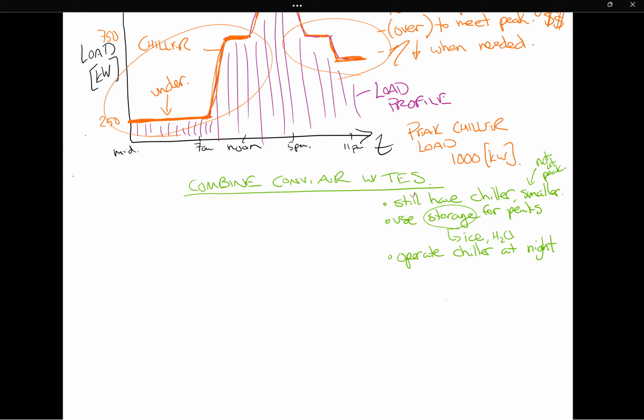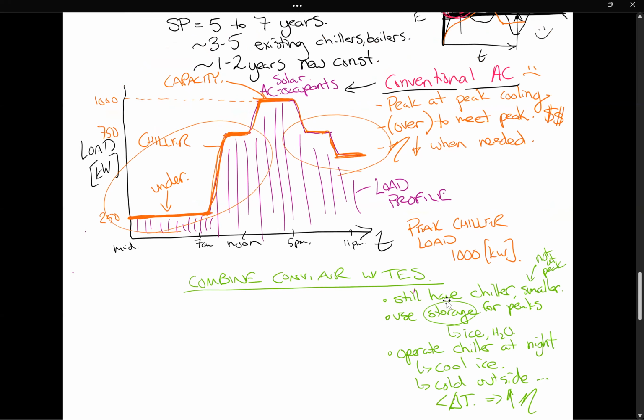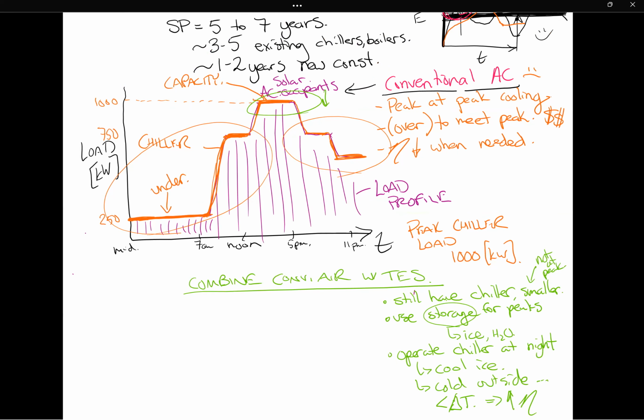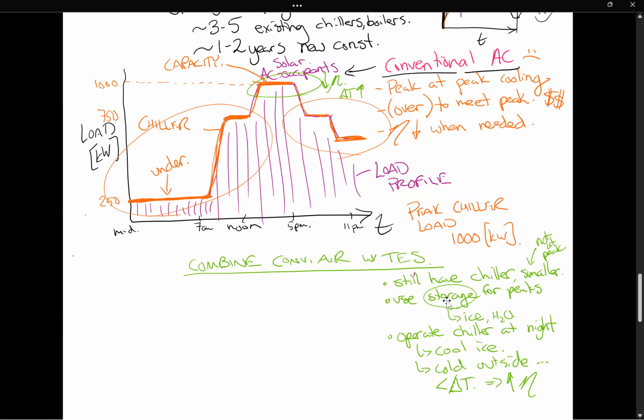Are your occupants going to feel that chiller at night? No. What's going to feel the chiller at night? The ice — we use the chiller to cool the ice. It's going to be cold outside, and if it's cold outside, that means there's a smaller delta T. If there's a smaller delta T, that means there's an increase in efficiency. Actually, that's why this chiller operates at lower efficiency here — because the delta T, the temperature between ambient air and outside air, is very high.